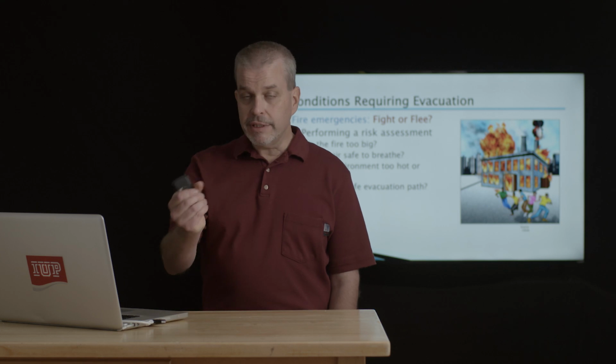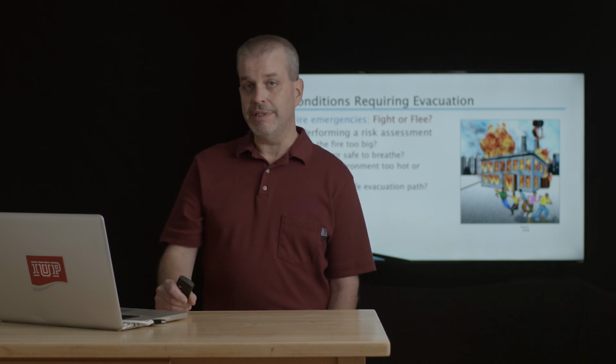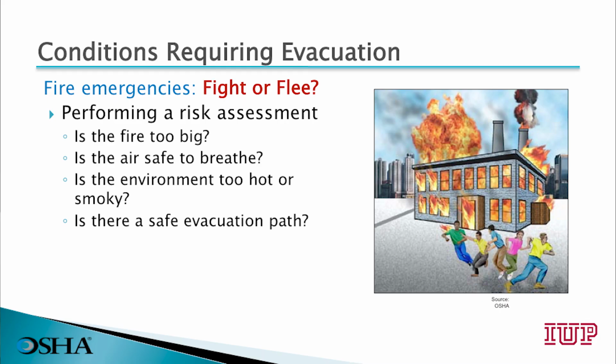So we need to do a risk assessment in order to answer this question: do we stay and fight or do we flee? If we are designated employees who are expected to remain behind to fight this fire, we need to ask ourselves, is the fire too big? Is the air we're breathing hazardous? Is the environment we are in too hot or too smoky? Or is our evacuation path potentially blocked?